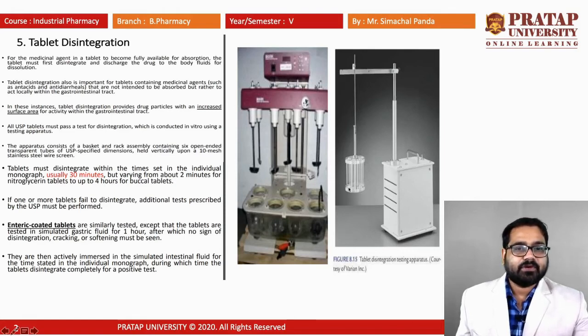The simple thing is, we take a beaker. This basket is attached with a motor. It will move to and fro. Inside, a 10 mesh sieve is present at the bottom of the tube. The tablet has to be present and move up and down. It is covered with a plastic disc that can move up and down, so it gives some pressure to break the tablet into small pieces and fragments. Slowly it comes out as the particles break. The time required to break is known as the disintegration time.